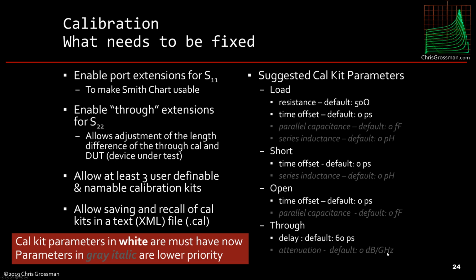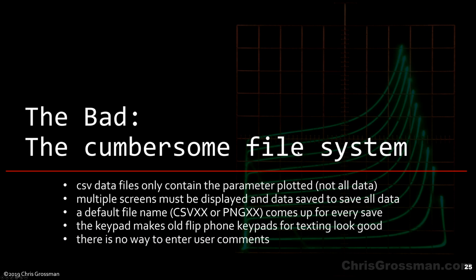So let's say I want to do a through calibration, but what I want to measure now, I'm going through a piece of cable whose losses I know. I can add those losses in and still get the measurements of what I want off somewhere else. So this is all stuff that should be added into the calibration kit.